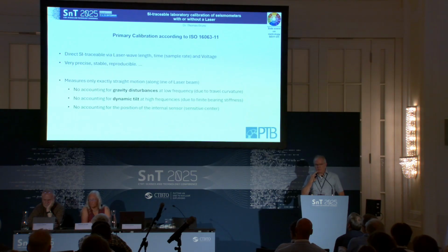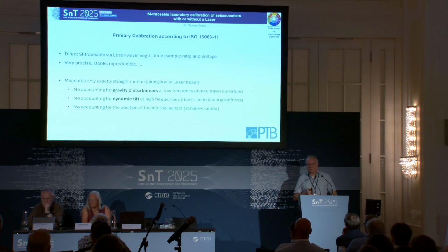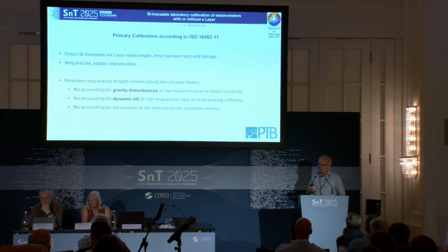look a little bit closer at this primary calibration, it is directly SI traceable. The laser wavelength gives you the length measurement. The time is given by the sample rate, and then you measure the voltage of the output of the seismometer with a traceably calibrated device, and that's basically all you need. It's very precise, stable, and reproducible, and we have very good and very long experience with that.